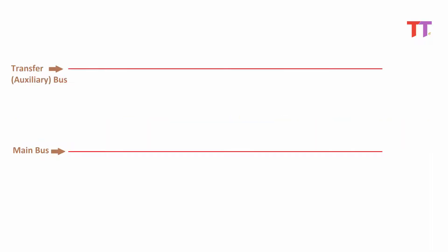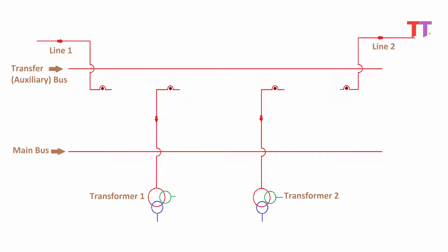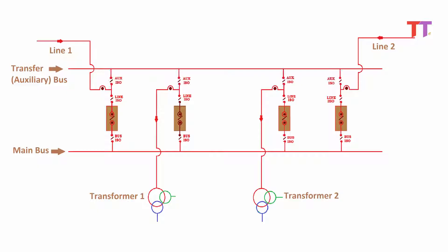3. Main and transfer bus system. As shown in the diagram, there are two buses — one main bus and one transfer bus, also called the auxiliary bus. Each bay or equipment such as line or transformer is connected to both buses: to the main bus through a circuit breaker and isolators, and to the transfer bus through an auxiliary isolator only. These two buses are connected by a circuit breaker and isolators called the bus coupler, and this bay is called the Transfer Bus Coupler (TBC) bay. In normal condition, the load of all bays is on the main bus and the transfer bus is in standby mode, meaning auxiliary isolators are open. Also, the TBC bay circuit breaker and isolators are open.